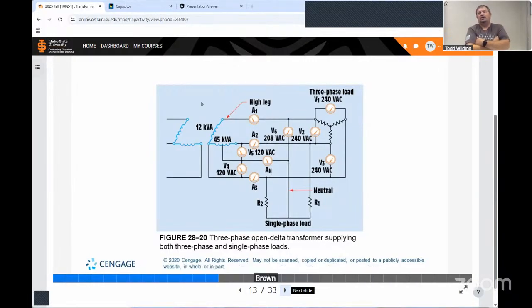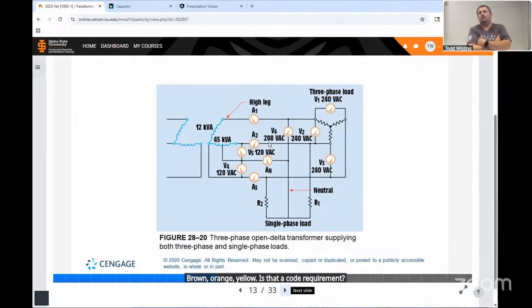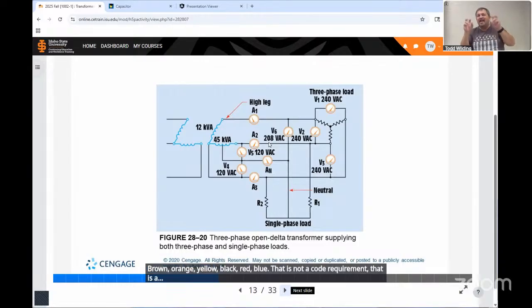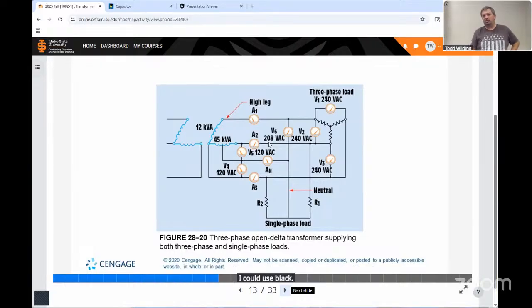Brown, orange, yellow. Is that a code requirement? Brown, orange, yellow, black, red, blue. That is not a code requirement. That is a standard amongst the electricians. I could use black, orange, purple to color code my phases if I wanted to. But the standard amongst the trade is black, red, blue, white for a 208 120 volt system. A 480 277 is typically brown, orange, yellow, gray.